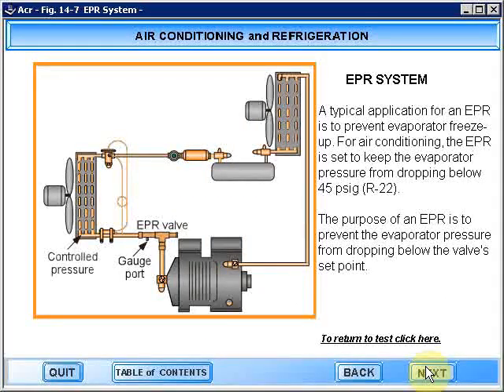A typical application for an EPR is to prevent evaporator freeze-up. For air conditioning, the EPR is set to keep the evaporator pressure from dropping below 45 pounds. That's with R22. The purpose of an EPR is to prevent evaporator pressure from dropping below the valve's set point.